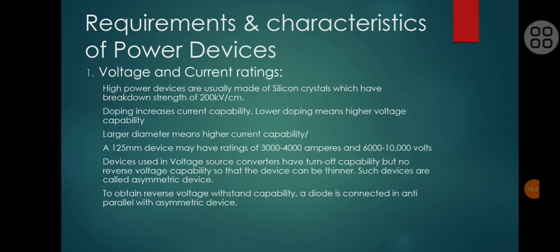Finally, the requirements and characteristics of power devices. There are three requirements: voltage and current ratings, losses, and then finally parameter trade-offs. The voltage and current ratings of a typical 125 millimeter device are 3000 to 4000 amperes, and voltage ratings of 6000 to 10,000 volts. Normally, voltage source converters are used in the advanced FACTS controllers, in which the devices used are asymmetric turn-off devices which have turn-off capability but no reverse voltage capability. This feature is preferred because if there is no reverse voltage capability requirement, the device can be made thinner. Otherwise, it will be bulkier. And so, in order to obtain the reverse voltage withstand capability in an asymmetric device, you can connect a diode in anti-parallel.